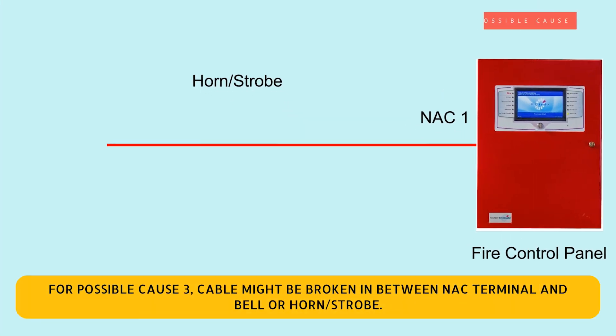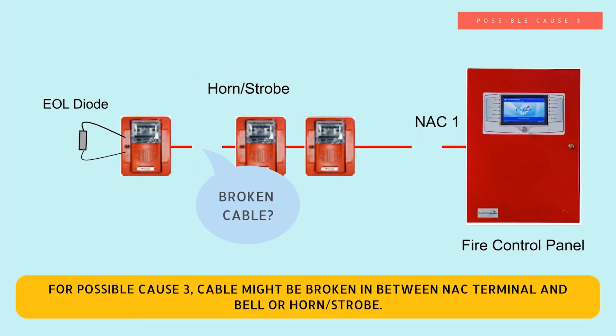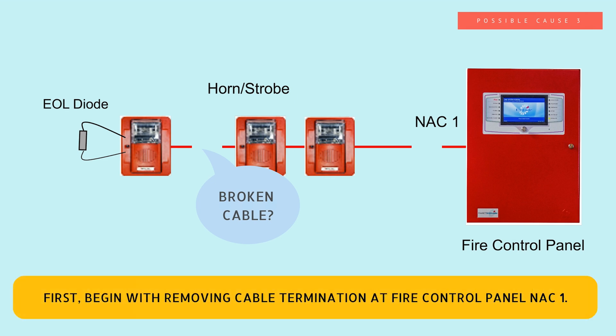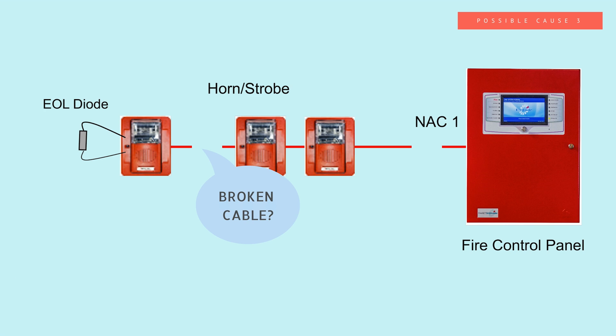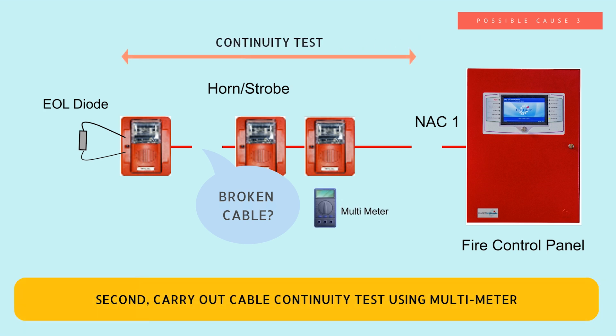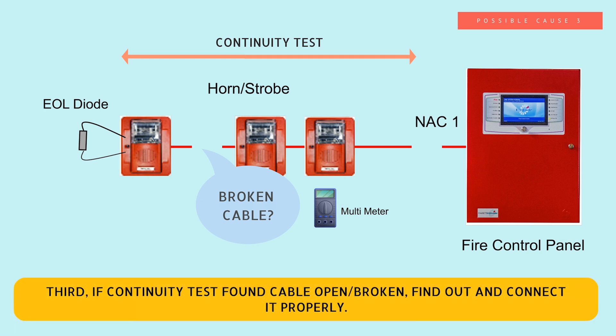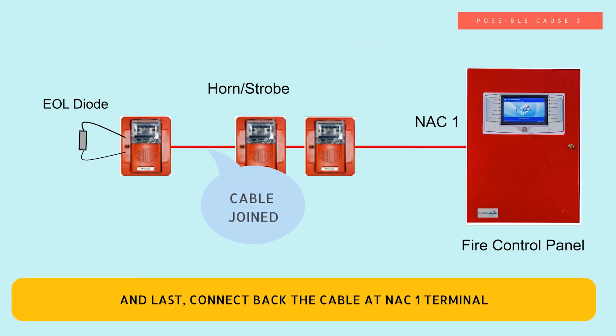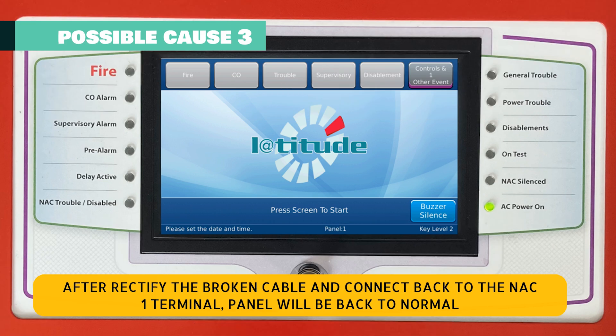For possible cause three — cable might be broken between the NAC terminal and the bell or horn strobe. First, remove the cable termination at the fire control panel NAC1. Second, carry out a cable continuity test using a multimeter. Third, if the continuity test finds the cable open or broken, locate and reconnect it properly. Finally, reconnect the cable at the NAC1 terminal. After rectifying the broken cable and reconnecting it, the panel will return to normal.